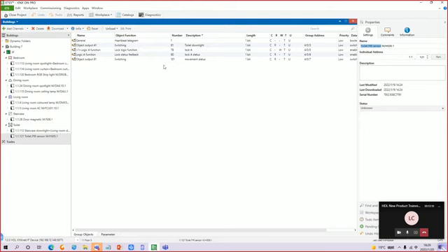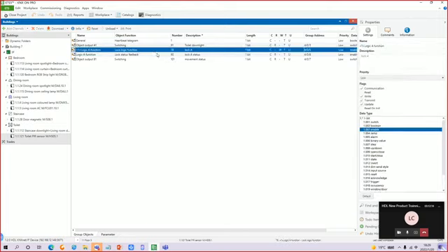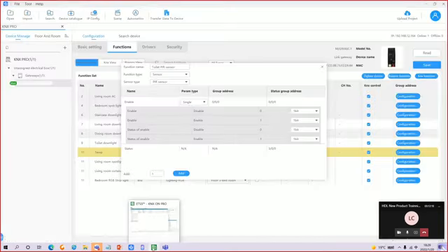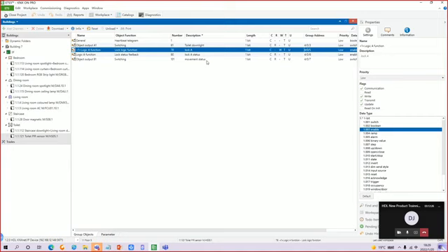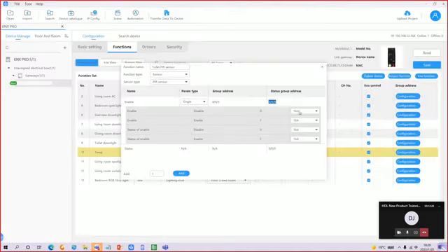And next, we can input the enable disable address, 405. And the status, 406. We also can configure the data type, 1 bit or 1 byte. It's 1 bit, so in here we select 1 bit and the value. When disable 0 and enable is 1. And also we can read the status from the PIR sensor.